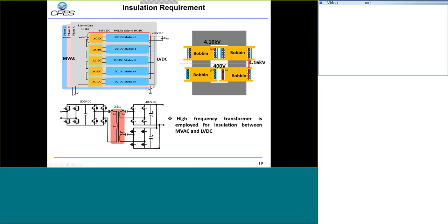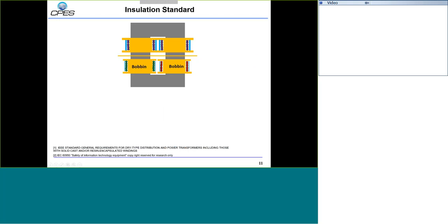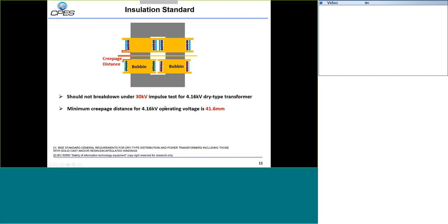Between the secondary-side winding and the bobbin, since the secondary side only stays at low-voltage DC 400 volt, we only need to satisfy 400-volt insulation requirements there. Based on these insulation requirements and following IEEE standards, if we use 4.16 kV as input voltage with a dry-type transformer, the transformer must withstand 30 kV — passing the 30 kV impulse test. According to the IEEE standard for this 4.16 kV application, the minimum creepage distance should be 41.6 millimeters.